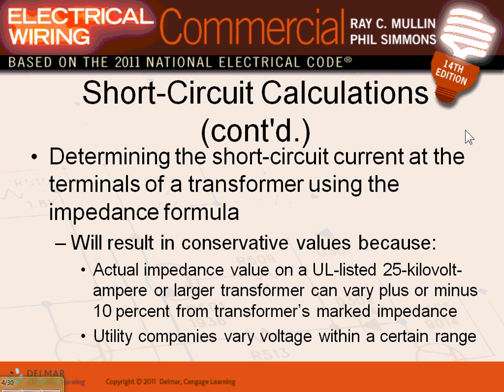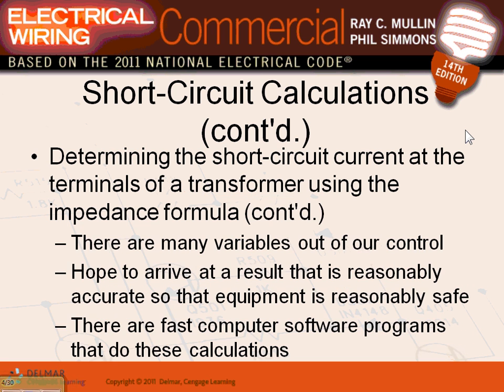Okay. When they do this, the start point for all the calculation is the transformer. The start point is always the source of the power, the transformer. I'll show you in a second. So for the transformer, suppose I have a 25 kVA transformer, you are allowed 10% plus or minus impedance. So you're going to see, we always start with the source, the transformer. You're going to see in a second here.